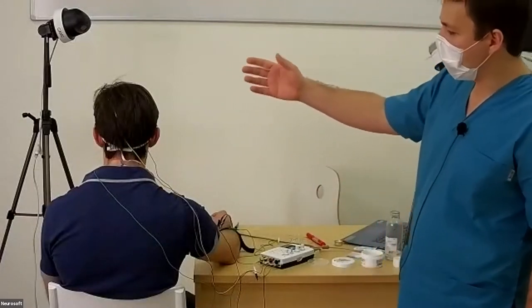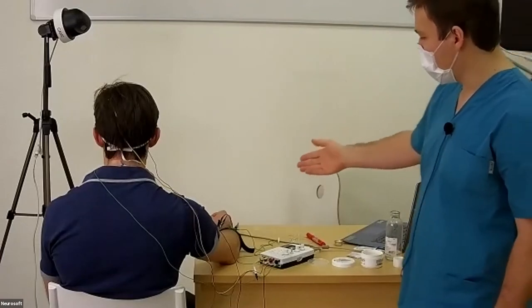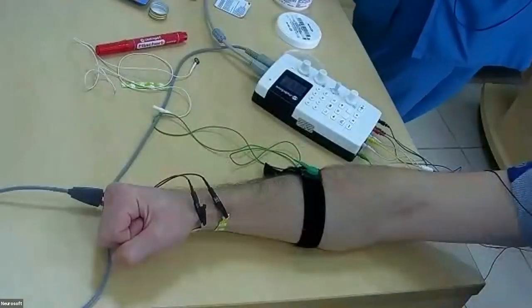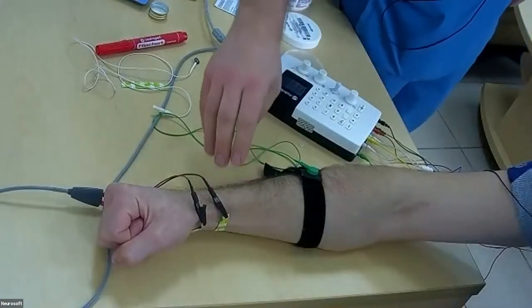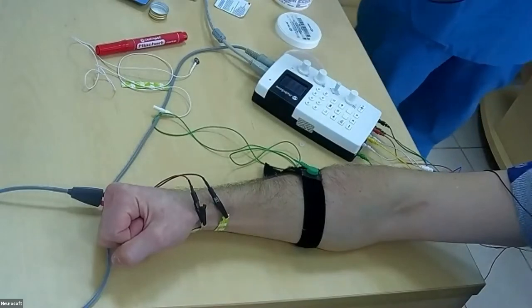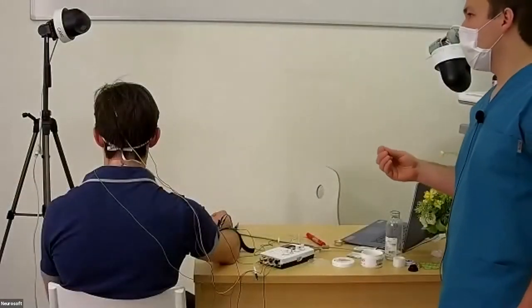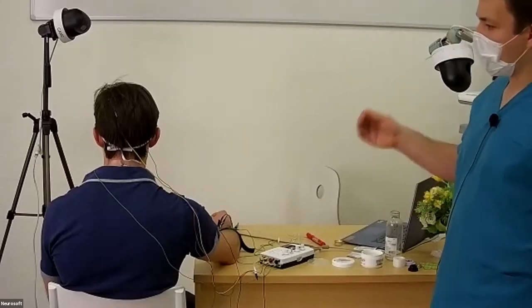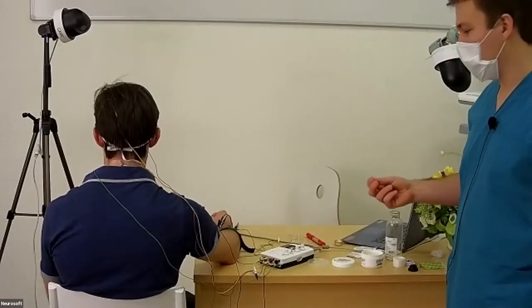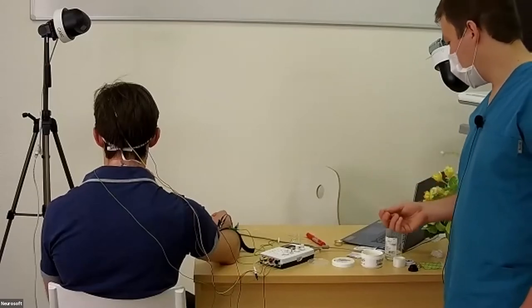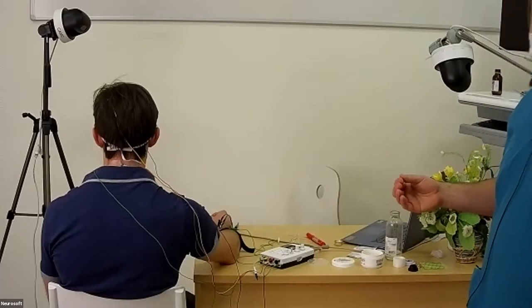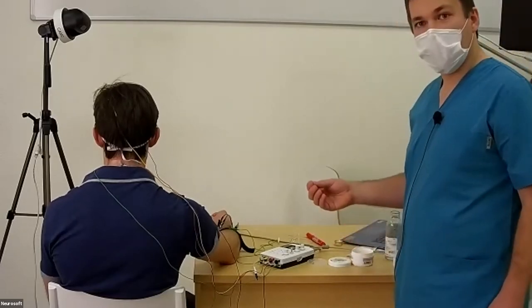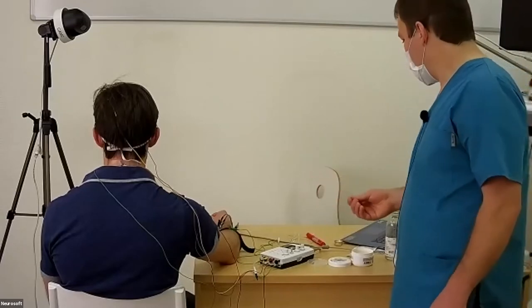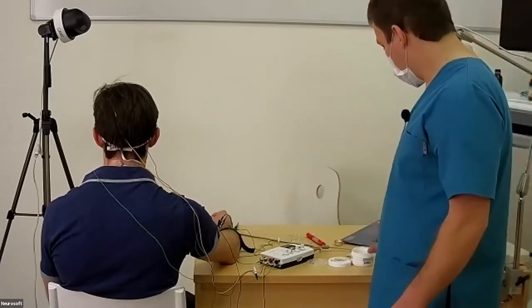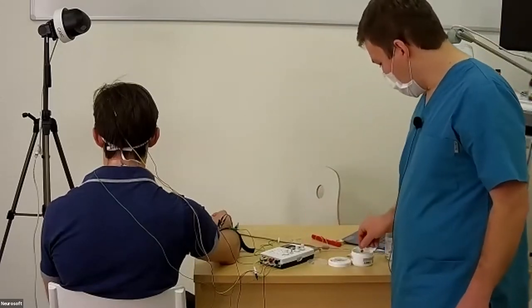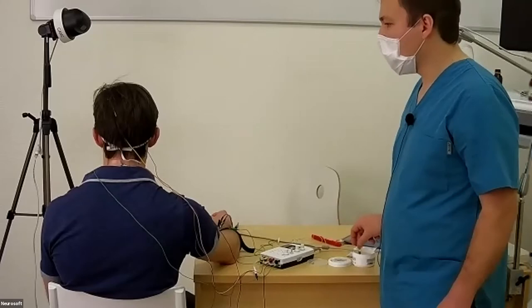We will illustrate somatosensory evoked potentials with median nerve stimulation. For registration, we usually need to use cup electrodes because we need very low impedance. So we need to very carefully prepare the skin. We should use alcohol and also some abrasive paste before setting electrodes, and after that we add cup electrodes with adhesive paste.